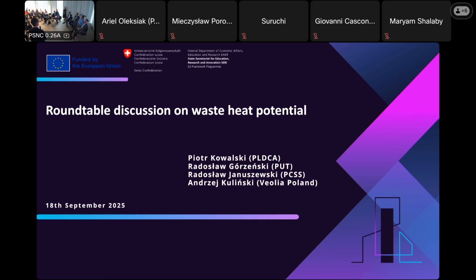I can show an example. We have the neighboring Poznań University of Technology campus. We have buildings with 90, 80 Celsius degree supply temperatures of the water system. But in parallel, there is a building erected three years ago where the supply temperature is 32 Celsius degrees. So when we talk about 30 or 40, it could be heated without any heat pump. That's the main idea of how we should think about it from the buildings' point of view.